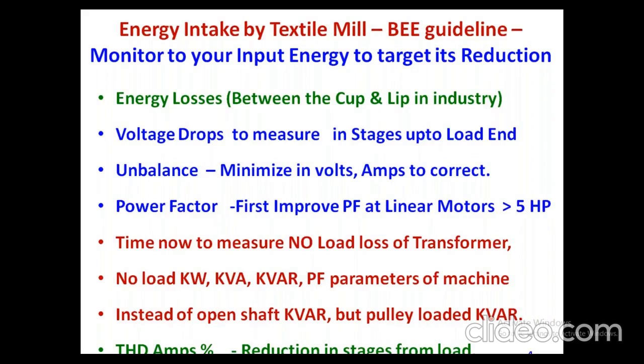The load and compensation, if it is done for any motors above 5 HP, suiting to the no load KVAR of the motors, the capacitor is sized to the no load KVAR of the motor, 90% of the no load KVAR of the motor.